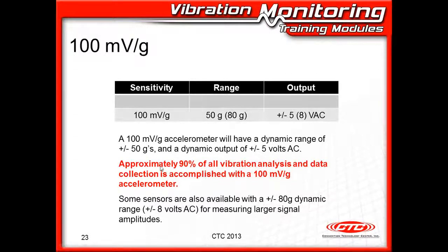This is the famous 100 millivolt per G sensor. As I've said here in the red block, probably 90% of all vibration analysis and data collection is accomplished with a 100 millivolts per G accelerometer. This is the popular one, the big seller. And it does come in 50 G and also in 80 G dynamic ranges.